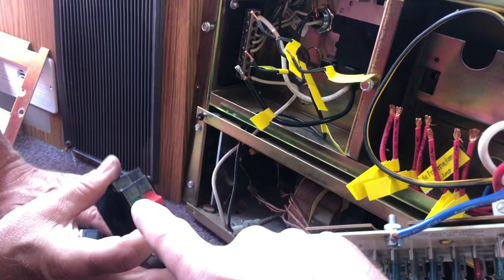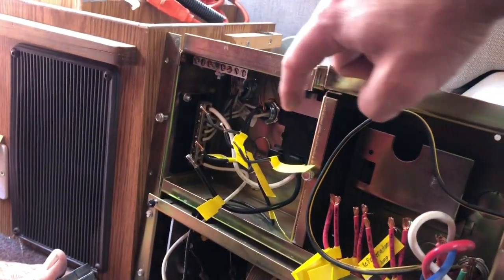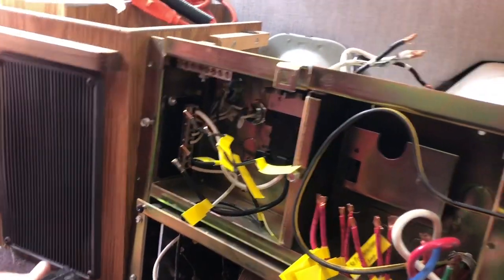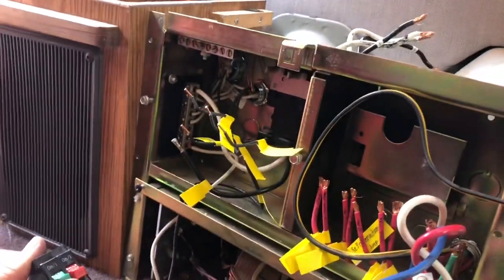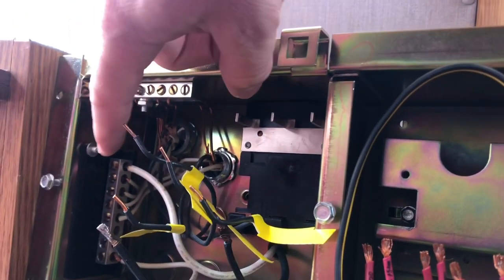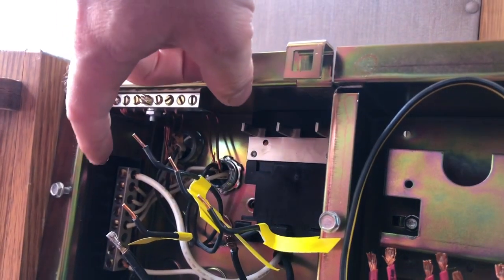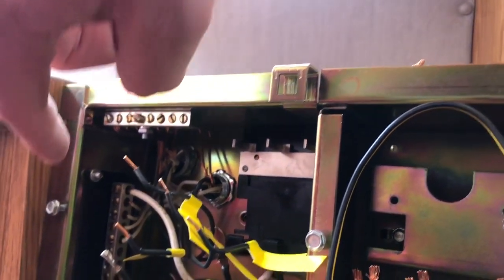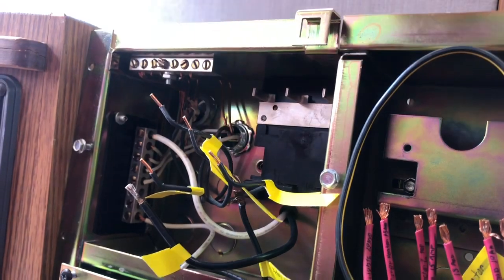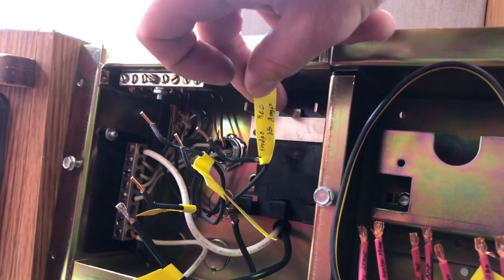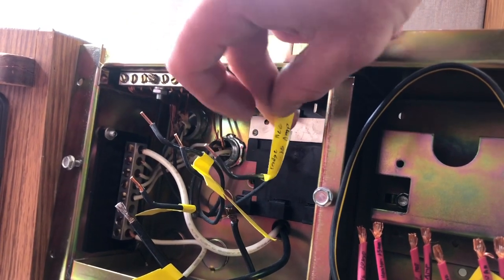That's your power switch, that's actually going through your 30 amp breaker there. That's going to backfeed the entire panel, so you'll get everything through that 30 amp. Wires removed from the breakers, and then up here on top you've got the grounds, and the white, that's your neutral. Those don't matter what order you put them back in, so I'm not labeling those. I'm just making sure the hot wires are all labeled, putting them back on the right side, and I put the amperage on there to make sure you're putting the right breaker on.